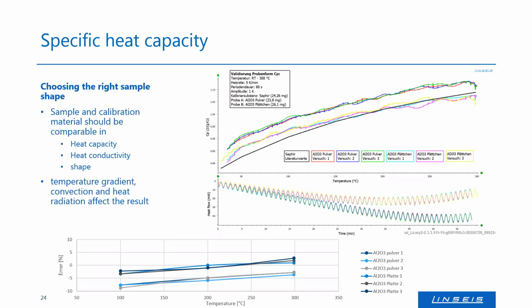But yeah, the specific heat capacity is basically the same. And this is what we can see here. A plate with a good shape at the bottom works much better than powder, because between the powder particles there's a lot of air, and so the heat transfer is pretty poor. So the shape and the condition of your sample is also quite important for your investigation.